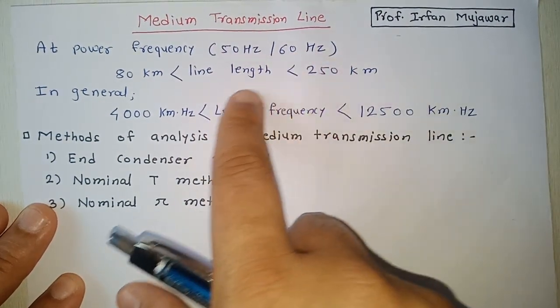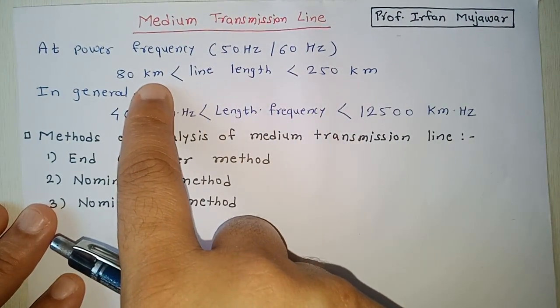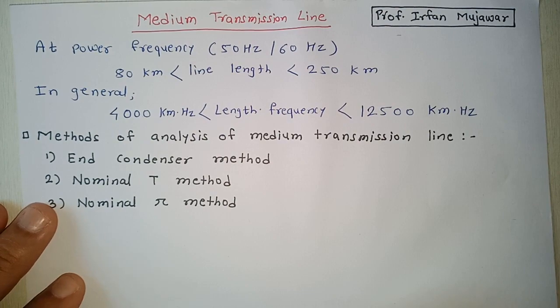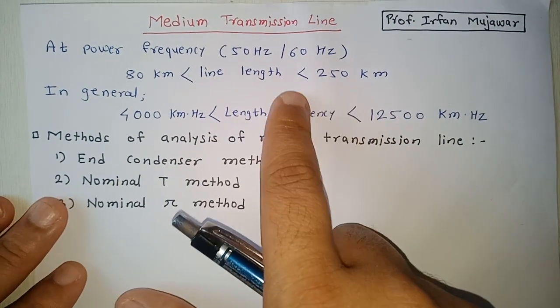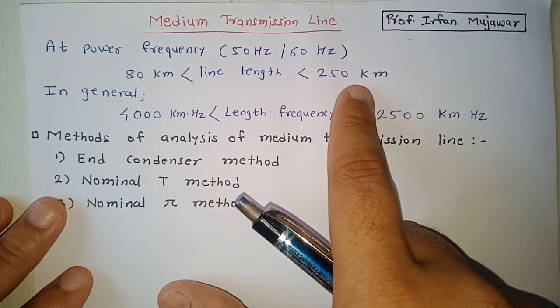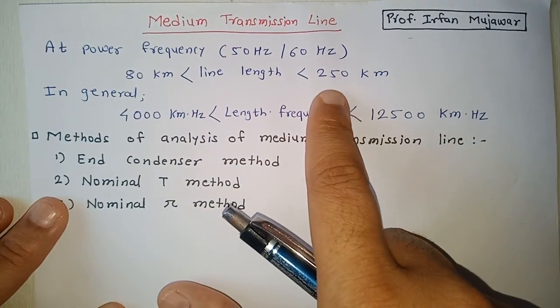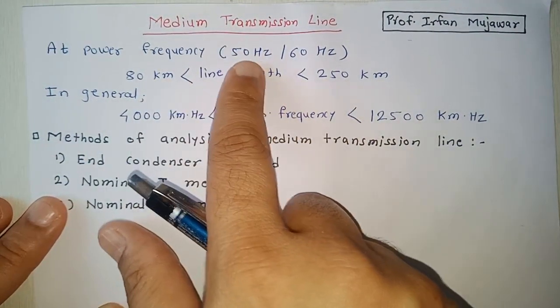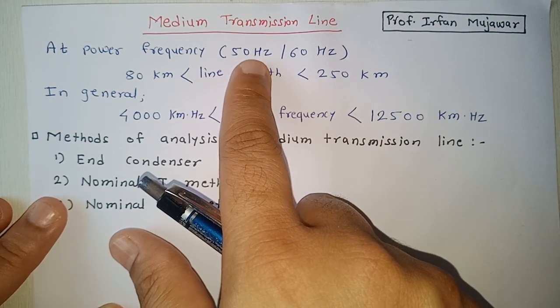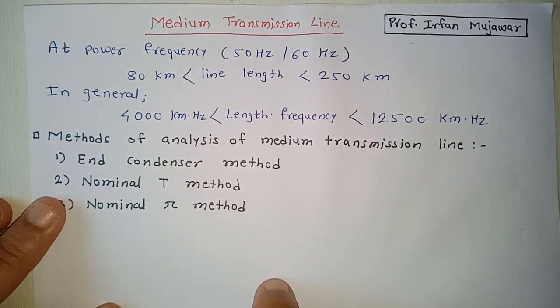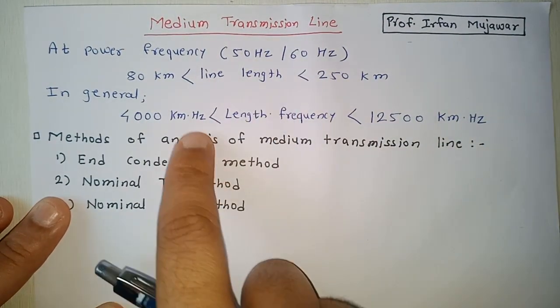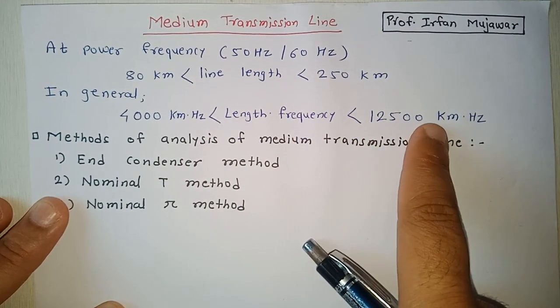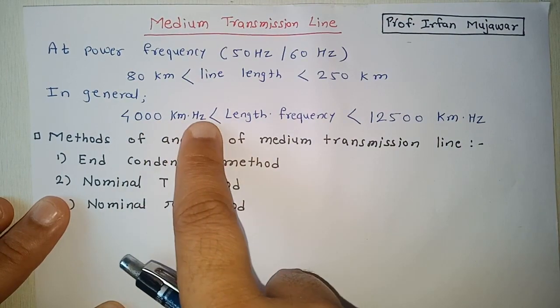At power frequency (50 Hz or 60 Hz), if the line length is greater than 80 km and less than 250 km, it is classified as a medium transmission line. In some cases, 250 km is taken as 300 km, but roughly we take line length less than 250 km and greater than 80 km.